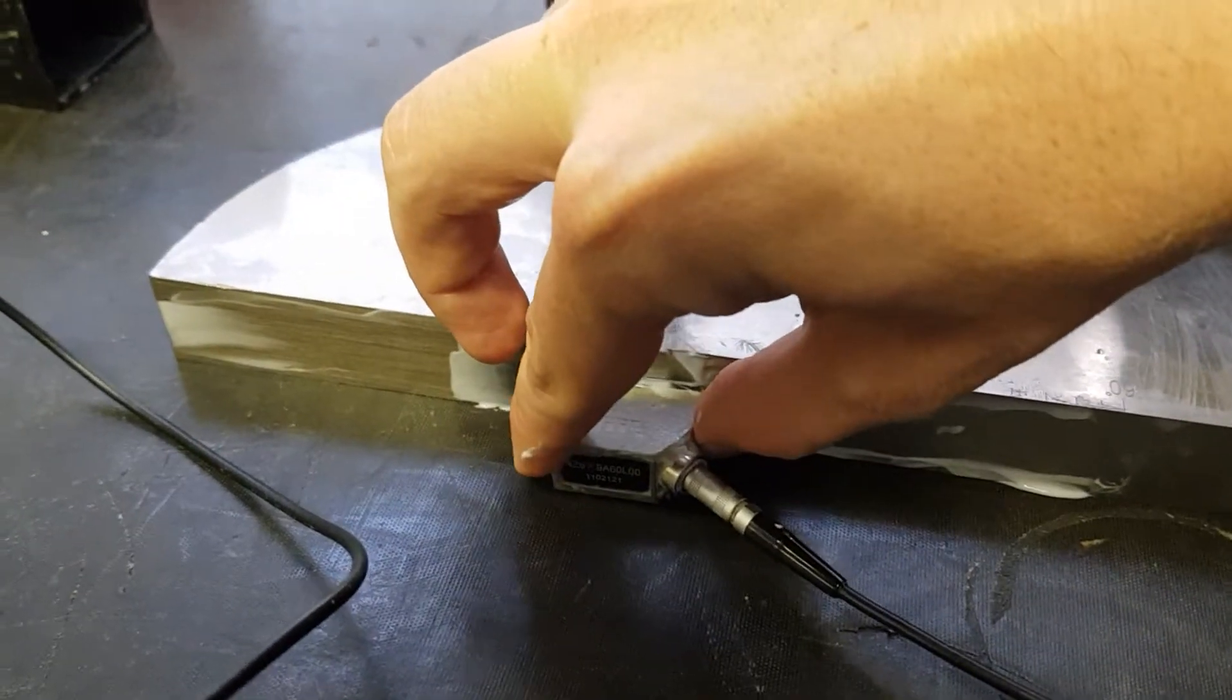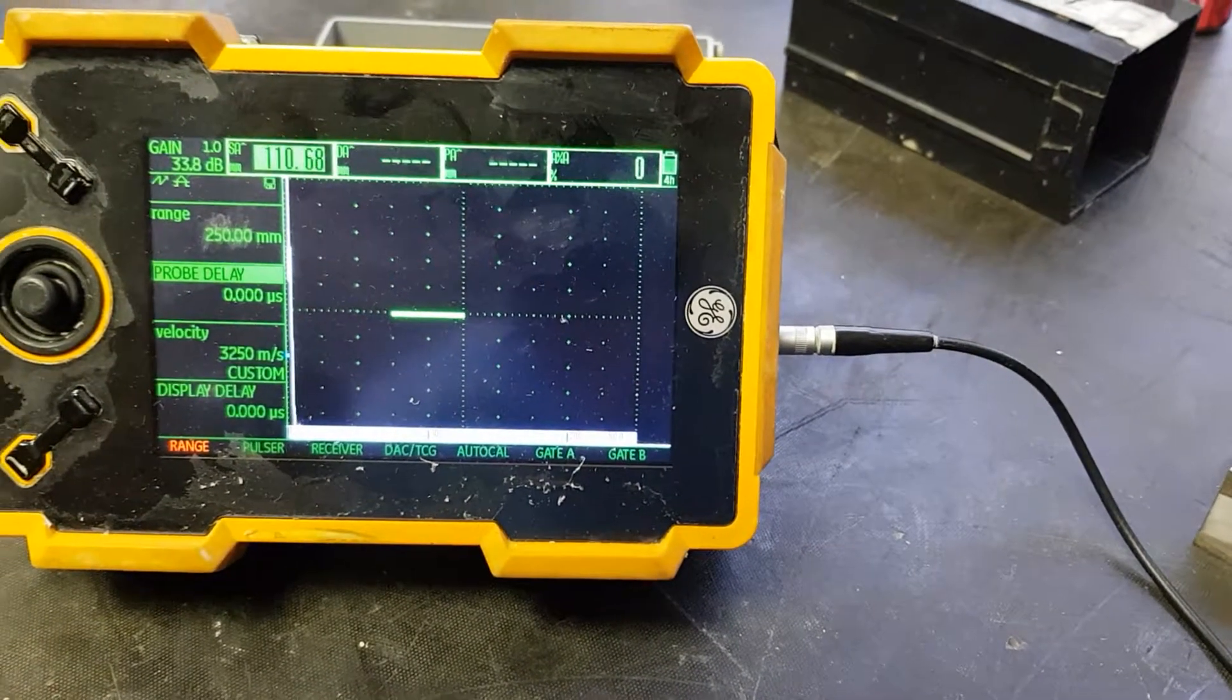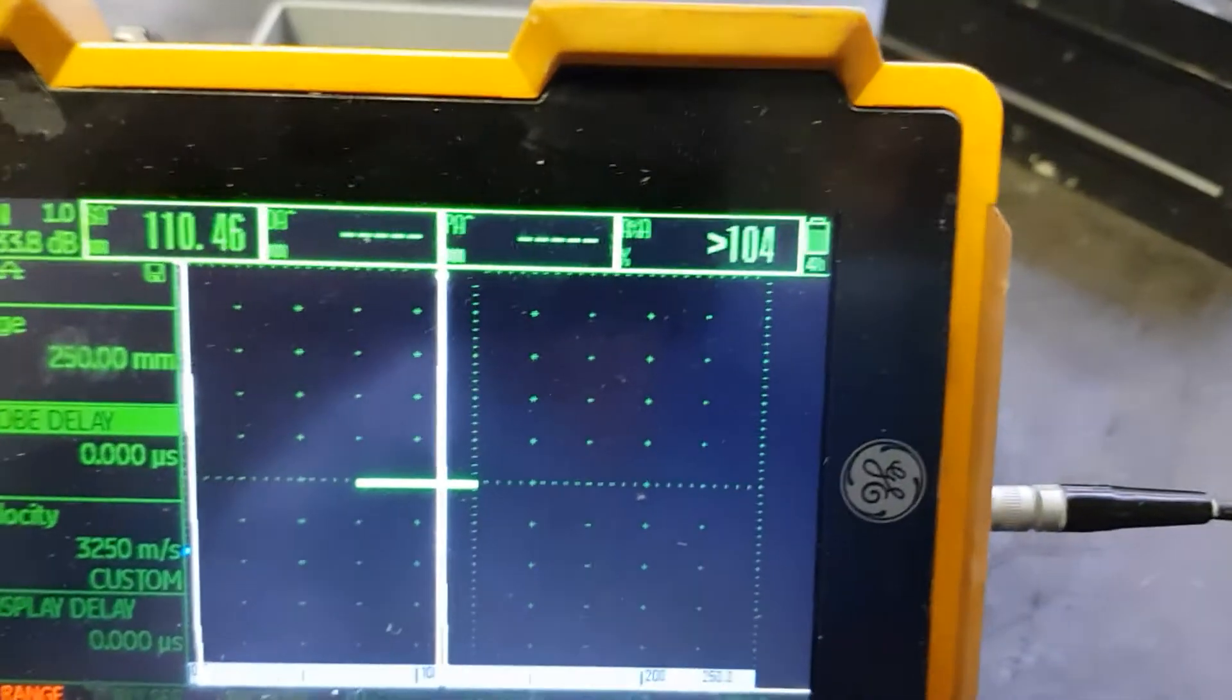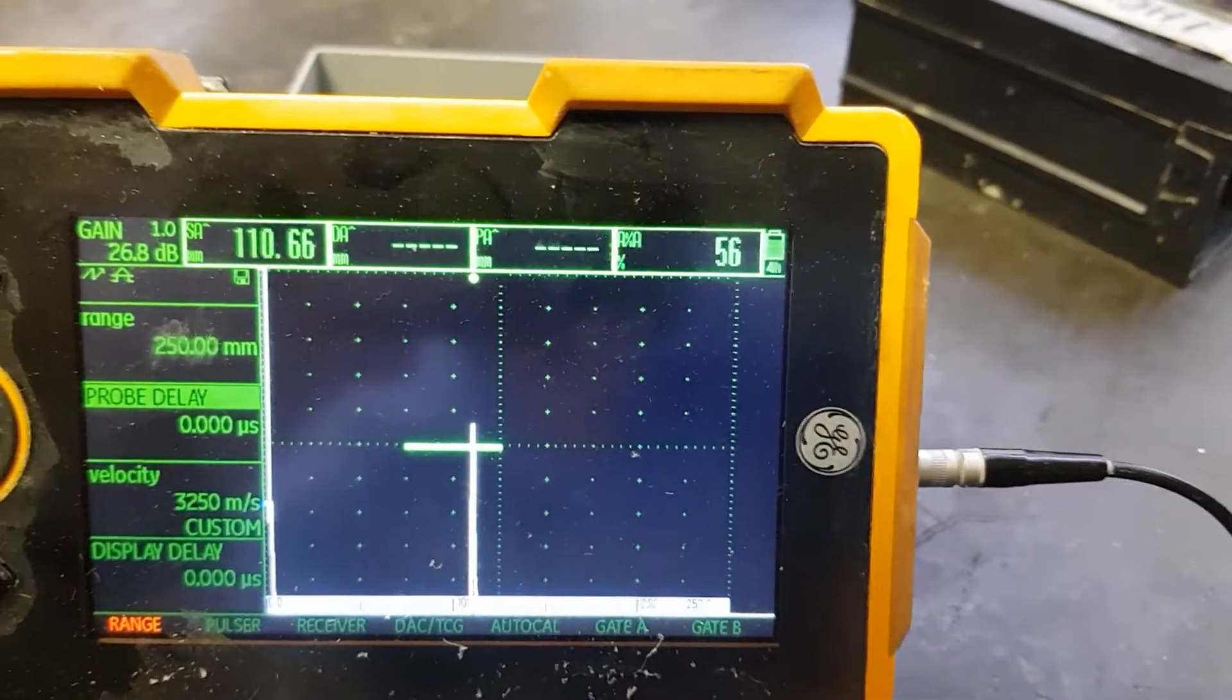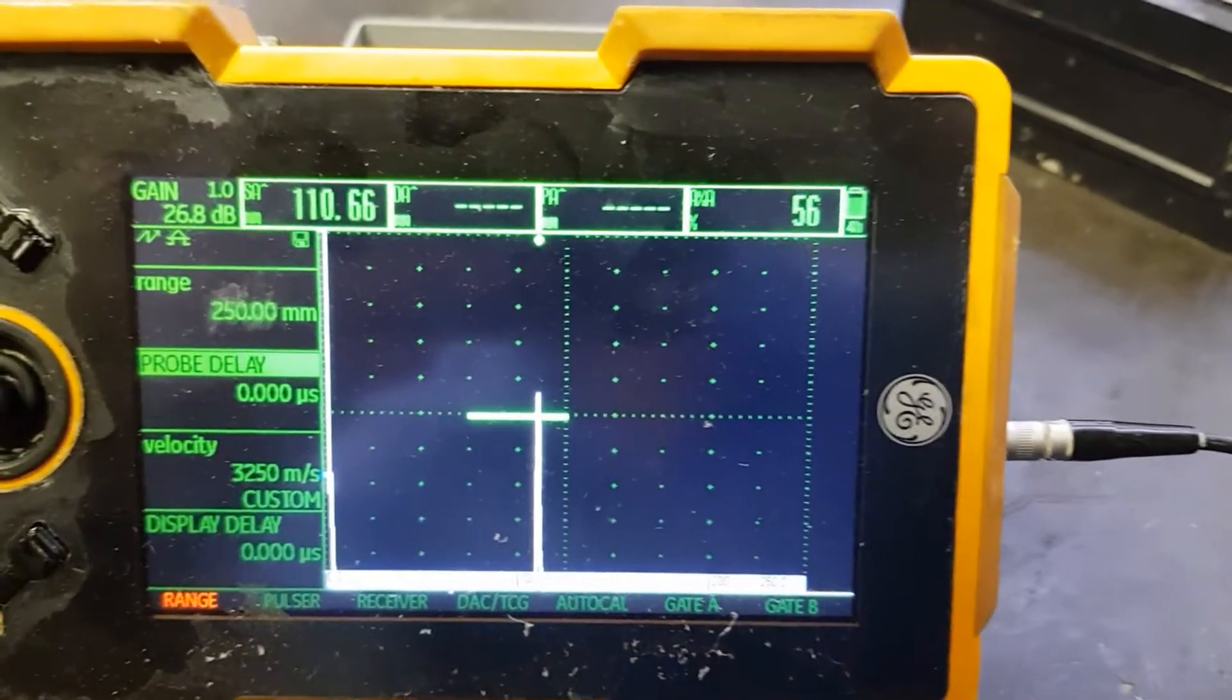As I move the probe forwards and backwards, an echo starts to appear on the screen. The problem is this echo is completely through the roof of the screen. I need to adjust the volume so I can actually see the peak. It's very important that you see the peak, otherwise you won't be able to calibrate your probe properly.